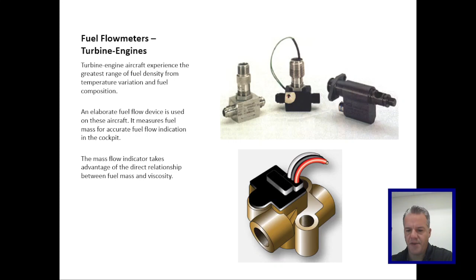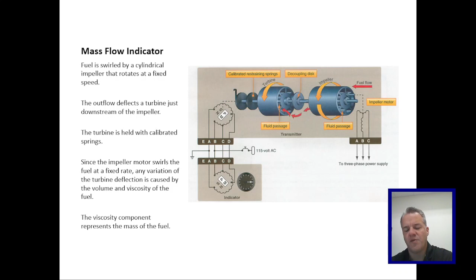Fuel is swirled by a cylindrical impeller that rotates at a fixed speed. The outflow deflects a turbine just downstream of the impeller. The turbine is held with calibrated springs. Since the impeller motor swirls the fuel at a fixed rate, any variation of the turbine deflection is caused by the volume and viscosity of the fuel. The viscosity component represents the mass of the fuel flow. So as you can see, the fuel comes in, it spins the turbine, and there are some calibrated springs. The difference between the speed of those is what's converted by the computer inside the gauge to give you the fuel flow.